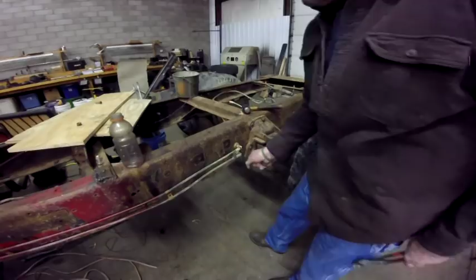Now these are the backside fittings for that tank heater, and technically these should be water. There should be no antifreeze in this, because that little unit up in front, which I'll show you in a minute, is a heat exchanger. So they wouldn't have, or shouldn't have, put antifreeze into the tank.